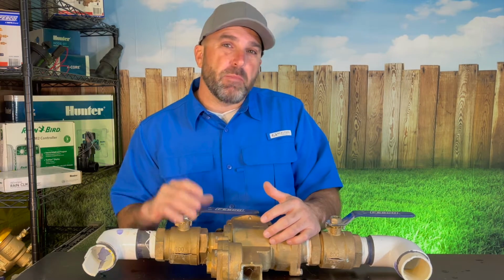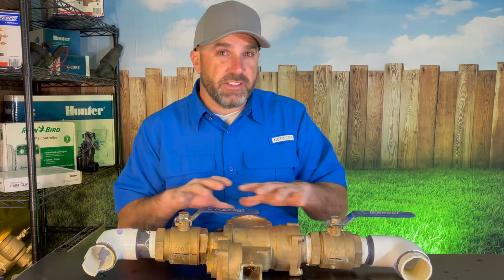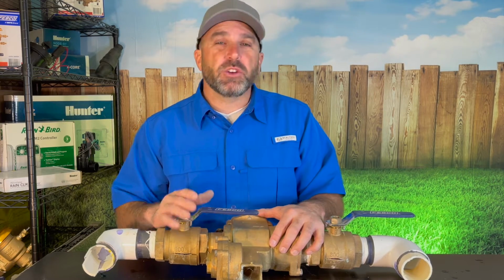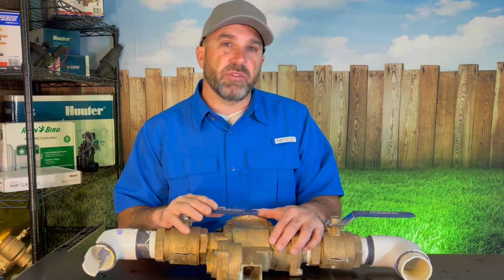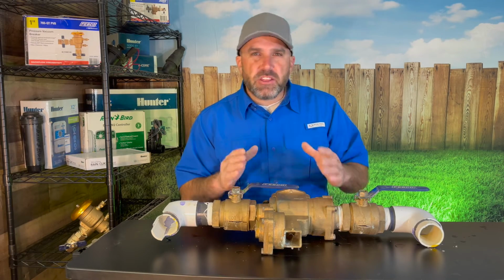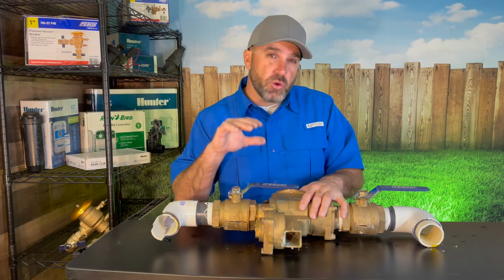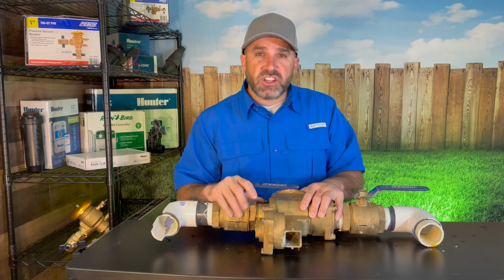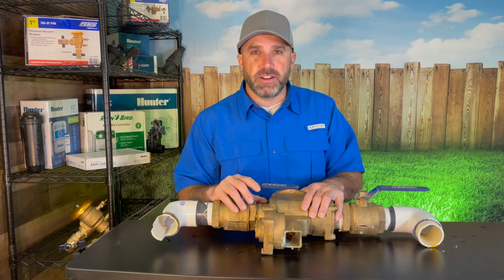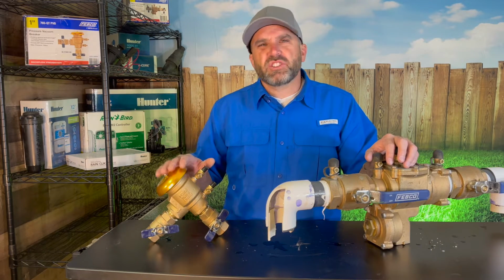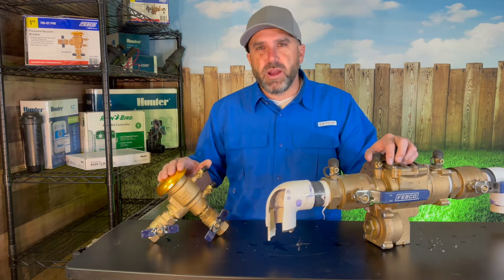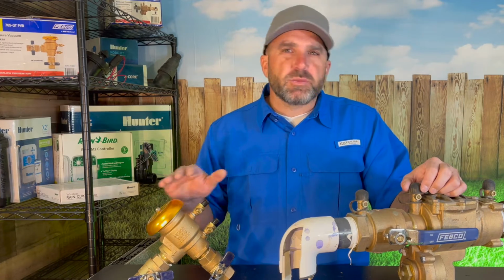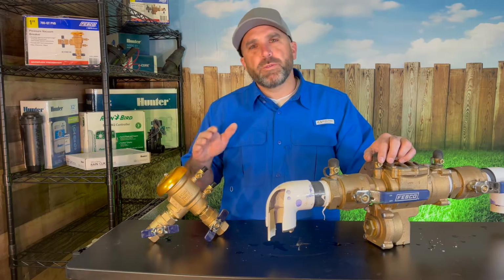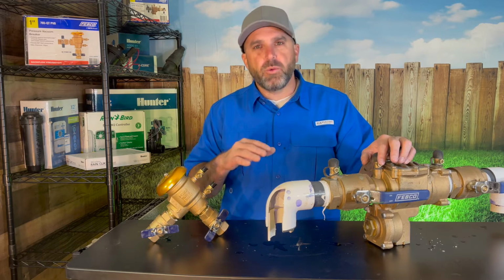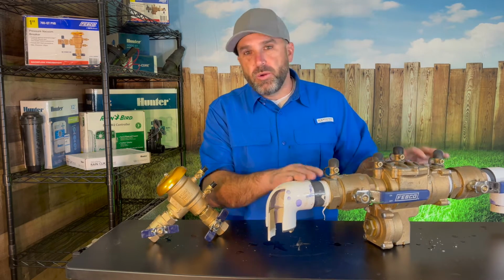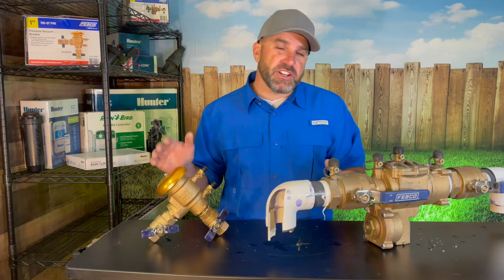These things are getting more and more expensive just to buy the unit itself, but it's also becoming more expensive to have them fixed and replaced. And so taking the precautions and doing something to winterize this is going to save you a lot of hassle and a lot of money in the long run. So let's talk about several things you can do to winterize your backflow device. If you're going to turn your sprinkler system off for the winter, one of the first things you're going to want to do is drain the water out of your backflow device, and you can actually drain it out of the entire system.